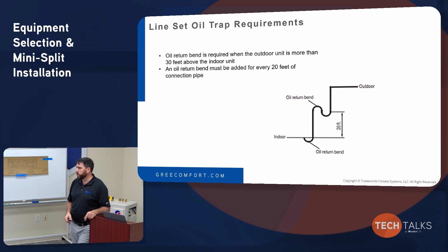One disclaimer: we'll talk about multi-pro tomorrow, and that oil trap rule does not apply to multi-pro. We don't do oil traps with multi-pro at all. This only applies to multi-zone, mini-split ductless, and single zone systems. To clarify today's training, we're only talking about mini splits, not flex, not multi-pro. We sell and support those too, but today we're only covering multi and single zone mini split systems, whether ductless, slim duct ducted, or cassette. Multi-pro and flex have different rules.